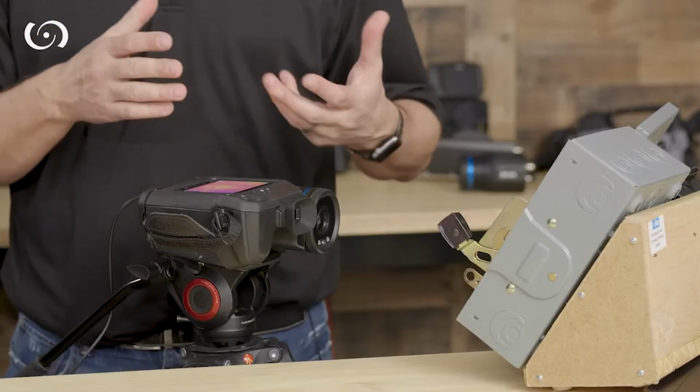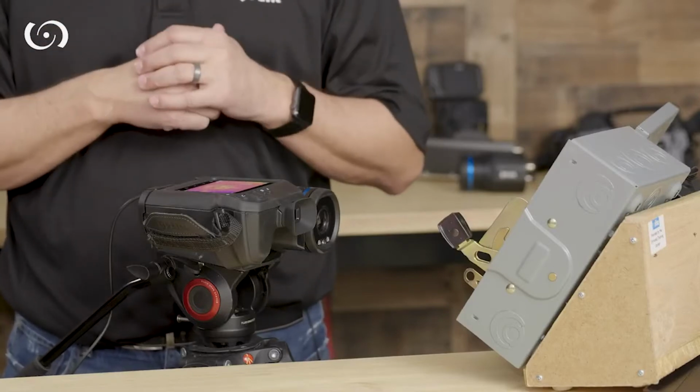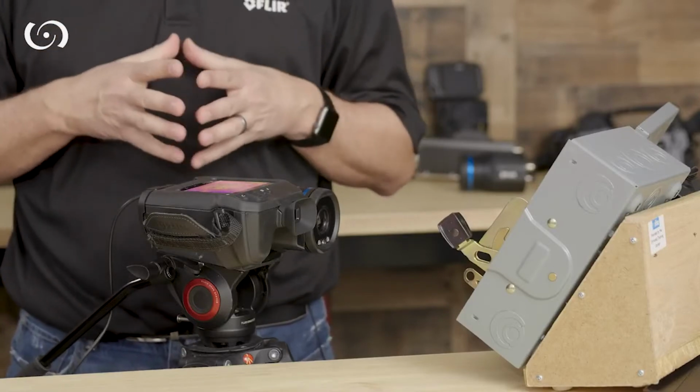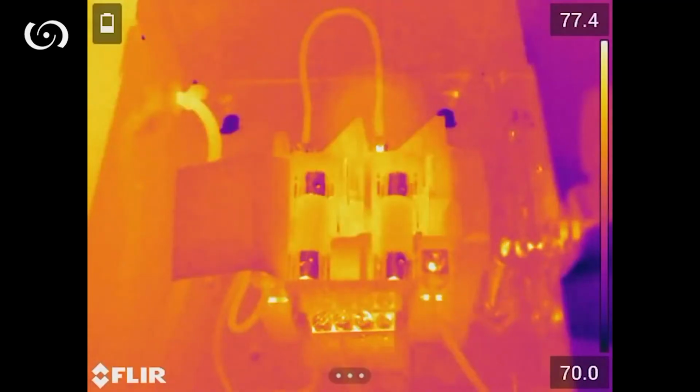With the camera, one of the nice things that we can focus in on is what we call one-touch level and span. Right now, we're in the auto mode. So what's happening right now is the camera's looking at the image and it's saying anything below 69.8 and 77 degrees Fahrenheit, it's going to continually optimize the image. That's why sometimes you'll see those change dynamically. So if I put my hand in front of it, you'll see the temperatures change very, very quickly.